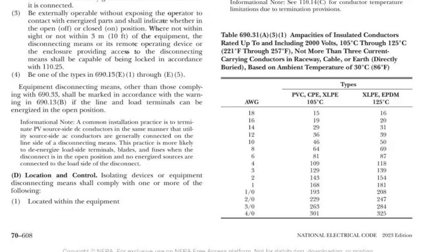So as you can see, we have some things that we might be familiar with already. AWG, American Wire Gauge. We have the gauge system that we understand. All the same ones up to 4-aught. 18, 16, 14, 12, all the same numbers all the way down. So the gauges are the same. What changes is the temperature of the insulation for these conductors. That's why I said you can't use the old conductors, because they have a different temperature or insulation rating.